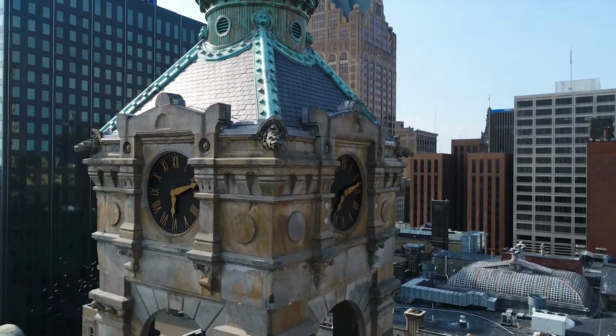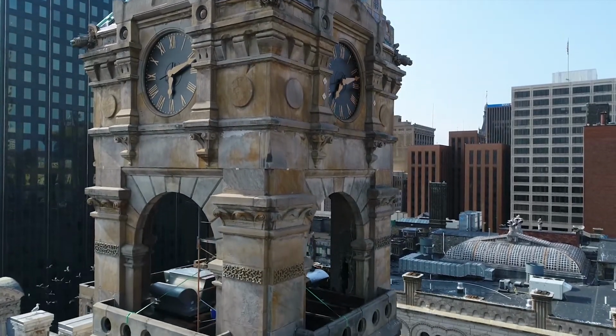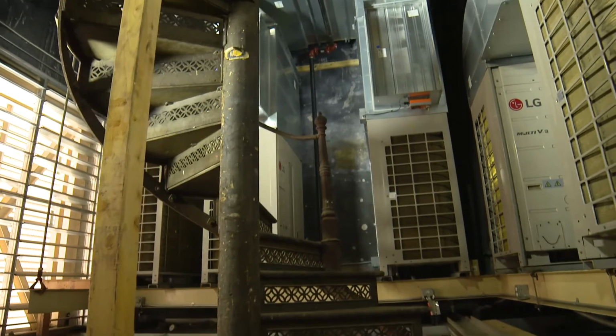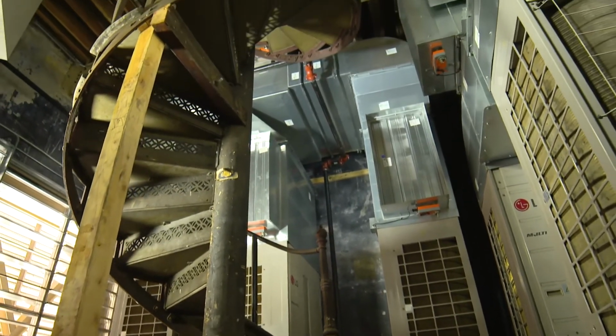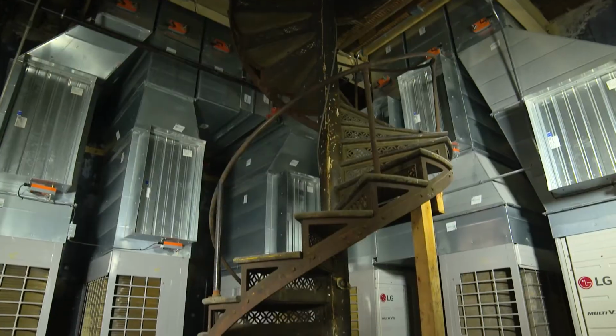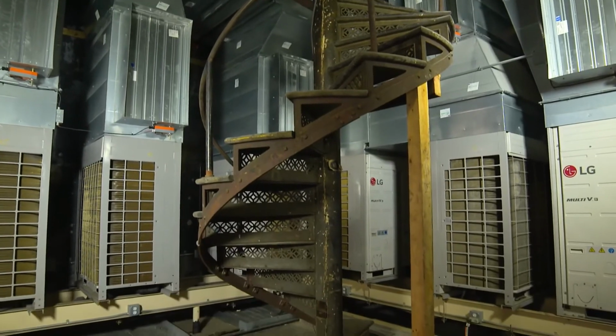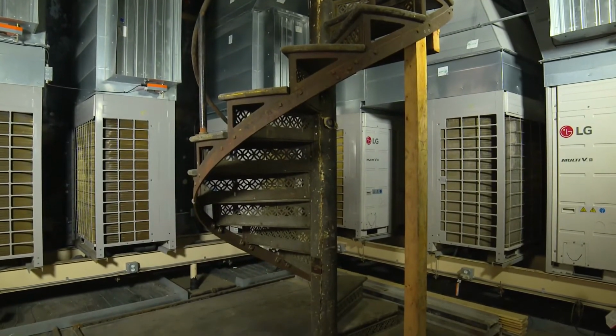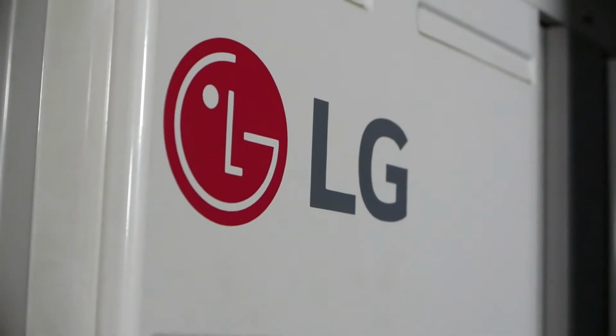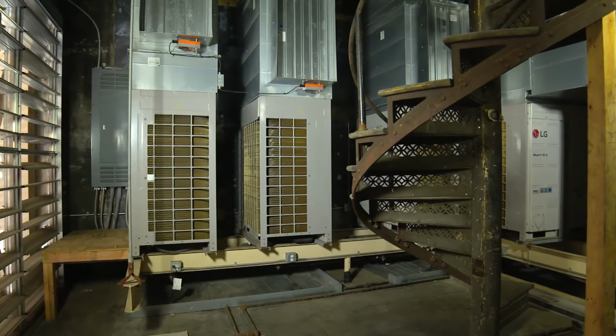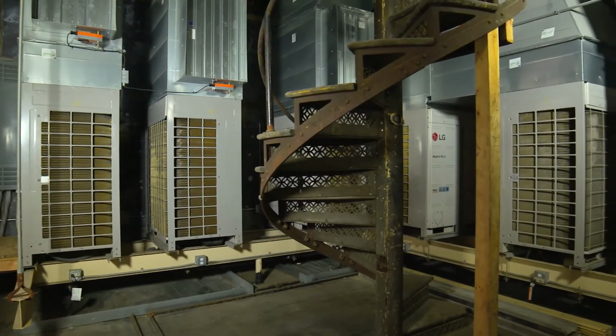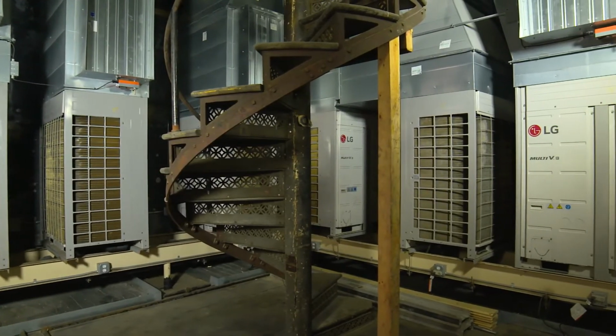So in this particular building, we were able to utilize the clock tower, and we were able to house our outdoor units in that space. And we identified it as an opportunity to locate the air-cooled condensing units inside and provide some heat in that space to meet the heating demands all the way through the wintertime. So we were actually able to use a VRF system without having a redundant heating source throughout the building. The LG VRF system is able to maintain an efficiency of above 3 COP, which is incredible performance in heating.